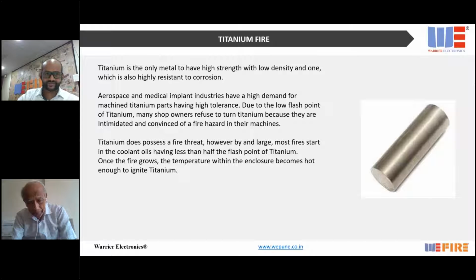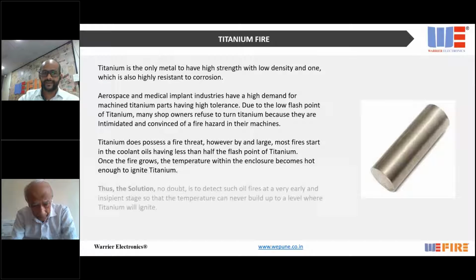Let me repeat the above paragraph once again. Titanium does pose a fire threat. However, by and large, most fires start from the coolant oils having less than half the flash point of titanium. So once the fire grows, the temperature within the enclosure becomes hot enough to ignite titanium. In most cases, titanium does not ignite on its own. It is the oil which starts the fire. Thus, the solution, no doubt, is to detect such oil fires at a very early, incipient stage so that the temperature can never build up to a level where the titanium will ignite.